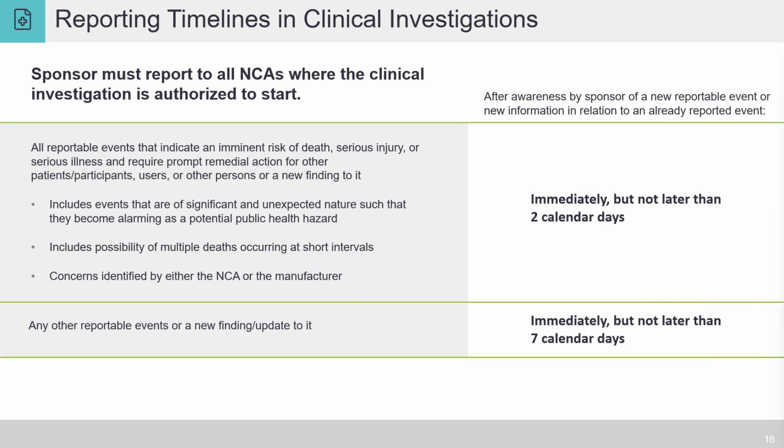We do prepare a safety management plan for clinical investigations in the device setup as well. And that should entail the stepwise action plan on the modus operandi from the SAE awareness date till the reporting is complete to the authorities, right from the site to the sponsor, the device case processing team, the regulatory reporting team. Everybody should be made aware, and that action plan has to be clearly documented in the SMP, safety management plan, to make sure that we are sticking to the timelines mentioned here for the clinical investigations. That's very important, and a lot of people do miss out on that while preparing the SMP, but that is an important aspect which we should always be careful of.